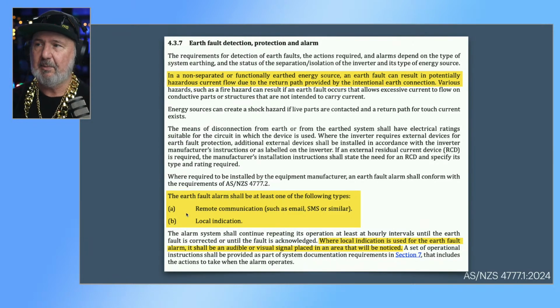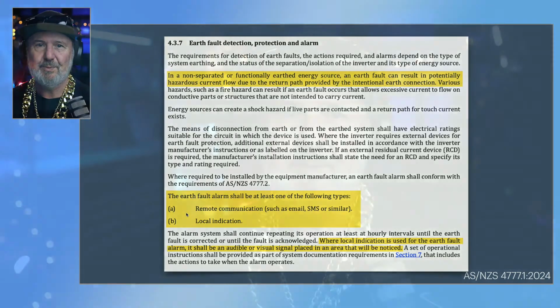And the second highlighted part there is outlining what the requirements for an earth fault alarm shall be. One of the following types. So this is interesting. It's actually a bit of a softening of the previous one, having an alarm that is both communication and audible or visual. Now we just give one of the following types. So it can be remote only, such as email, SMS or similar, or it could just be a local indication. Now, I must admit I'm a little bit disappointed by that clause, because local indication is probably more reliable than using email or SMS, because things change. People's email addresses change, their phone numbers change, and you may not even have internet on site. So having local indication, I think, is pretty good. It's really best practice, and it should be covered in the commissioning of the system with the installation, with the operator of the system to understand this.